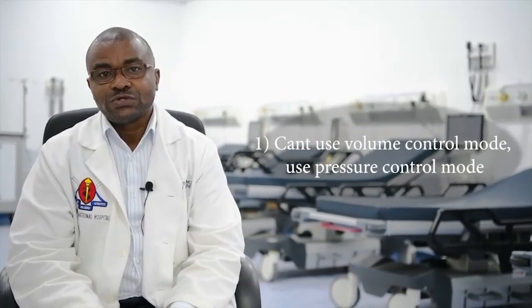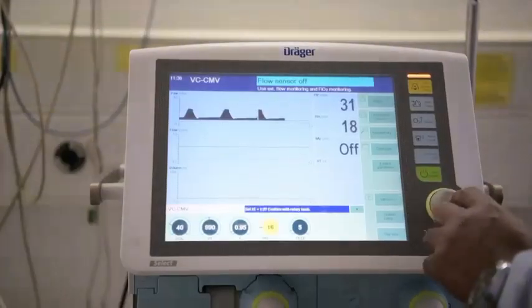One, you can't use volume control mode. You have to use pressure control mode.